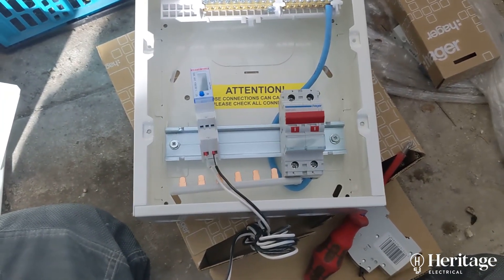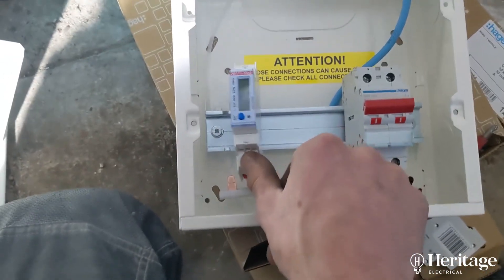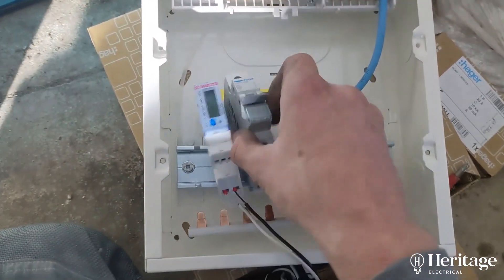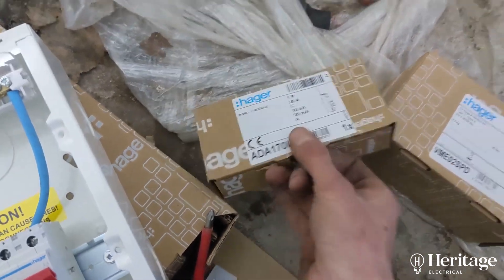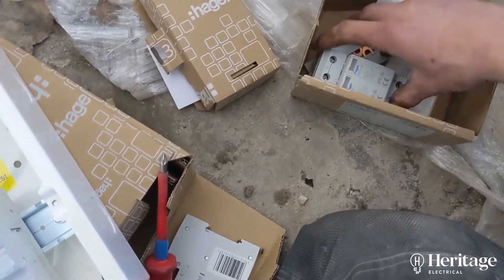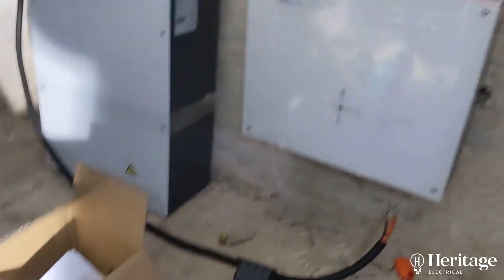So we've got our little Hager consumer unit here. Into this enclosure I can mount this meter, which is required for the inverter battery setup just to measure what's coming in and what's going out. That needs a six amp supply, so we'll fit an MCB in there. We've got a C20 RCBO to supply the actual inverter. And very importantly — it's now a regulation — any new board must have a surge protective device in there as well, just protecting all this sensitive gear.